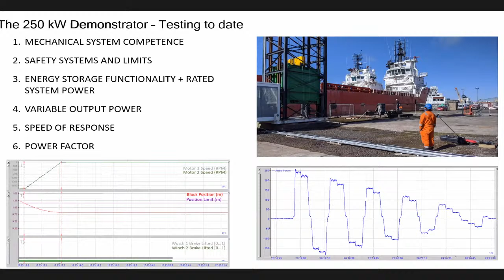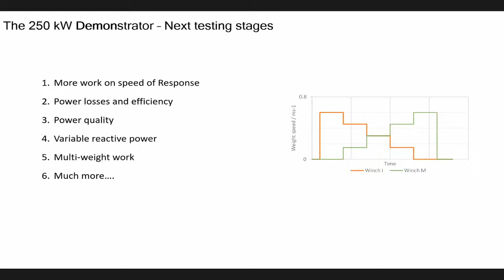Next stages with testing for this demonstrator are looking more at speed of response and trying to tune the system to improve it, looking at power losses and efficiency in both directions and round trip efficiency, looking at power quality - the harmonics of the system and how that affects the grid - and looking at how we can use the variable speed drive to dynamically change the power factor or reactive power generated by the system. Then there's testing where we move the two different weights separately up and down, smoothing and blending that output to give interesting results.